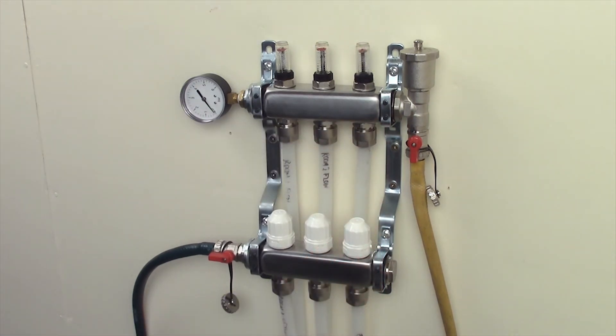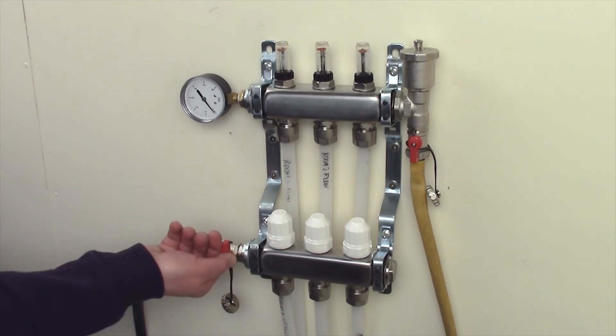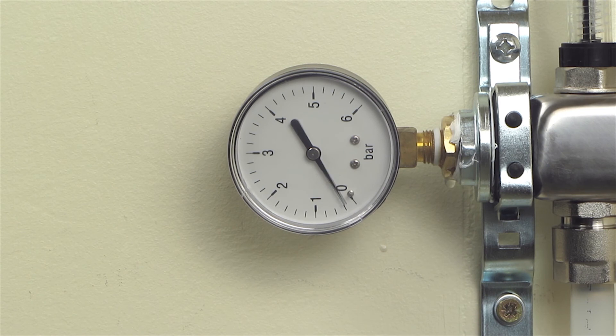Once all loops are filled with water and all air has been removed, close the drain cock on the bottom left return bar and allow the system to become repressurized up to four bar.